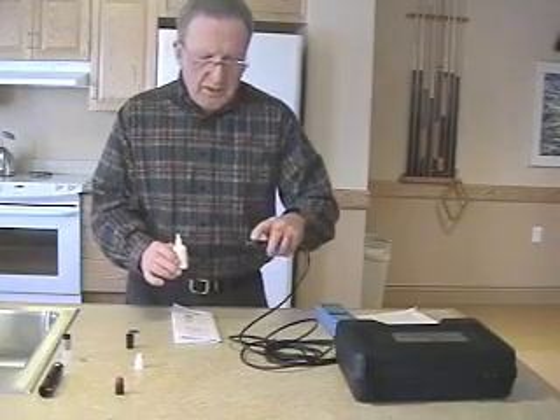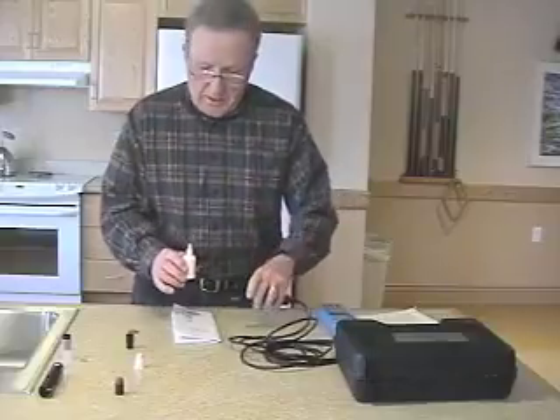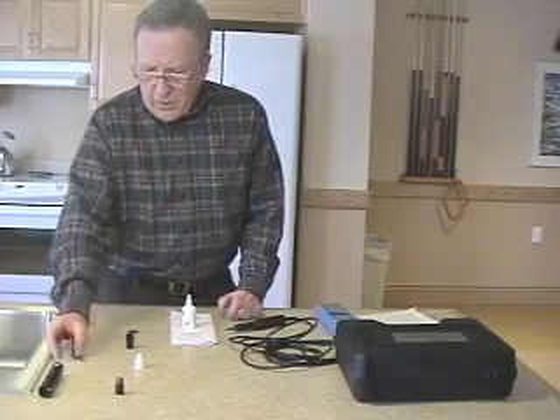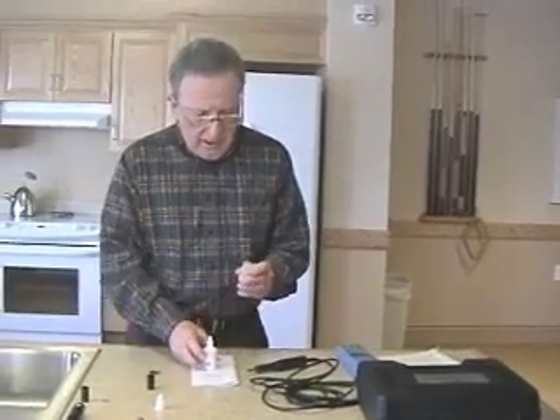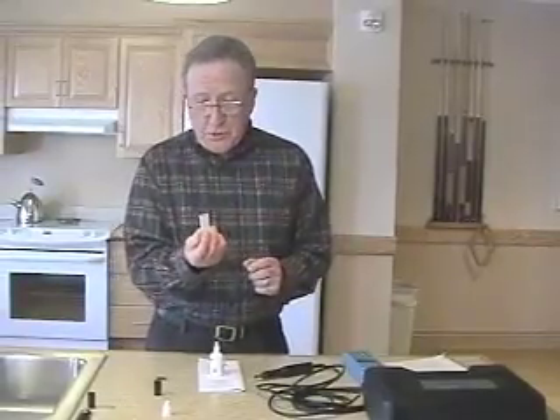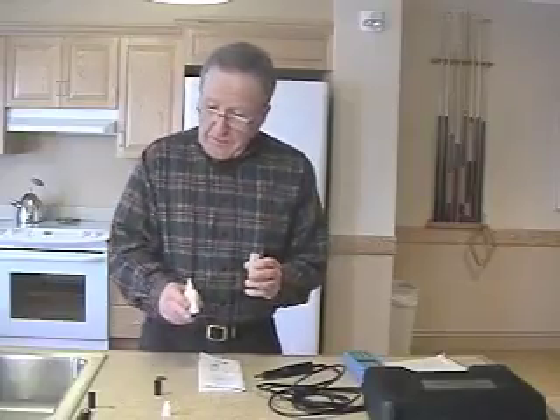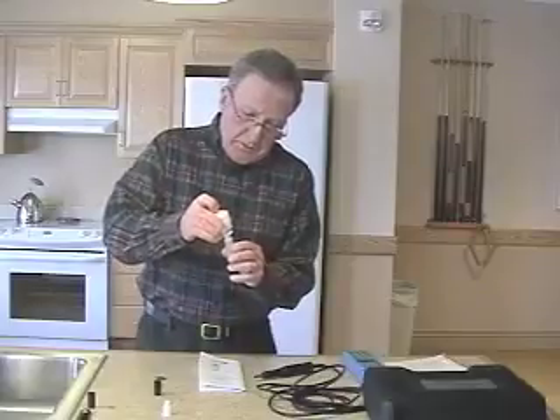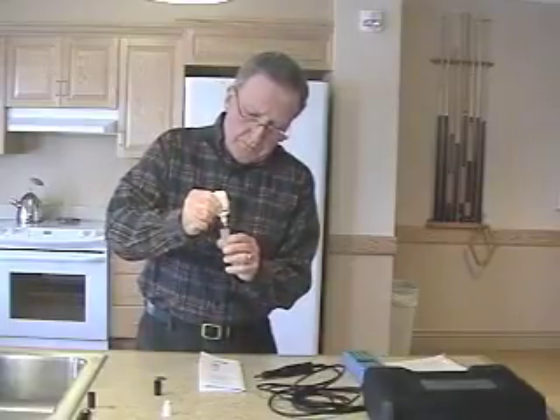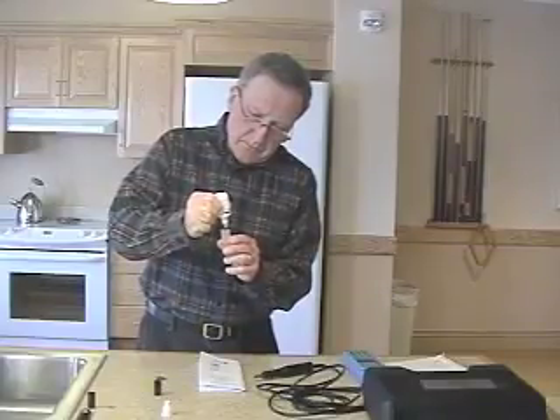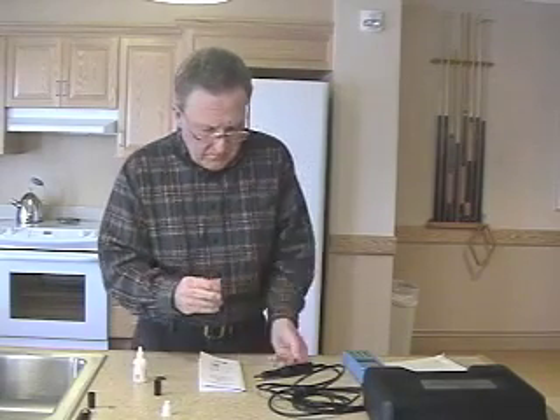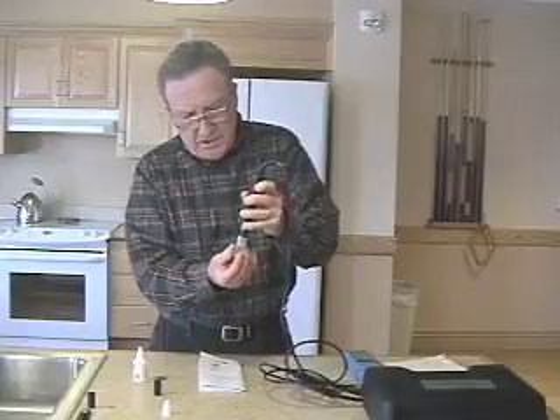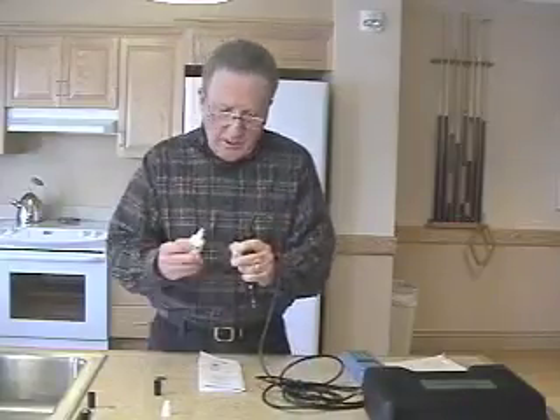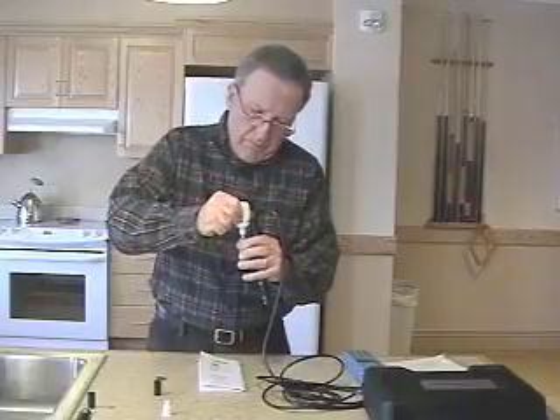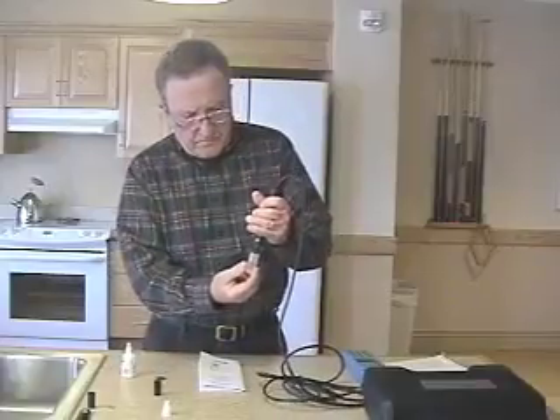Okay, to prepare the sensor, you need to soak the bottom inch of this tip in electrolyte for a 5-minute period. I think an easy way to do it, and it also saves on electrolyte, is to use the plastic storage cap for the extra membrane cap. So I'll put some fluid in there. Place the sensor down inside. I don't have quite enough. I'll need some more electrolyte. Okay, now we'll let that soak for 5 minutes.